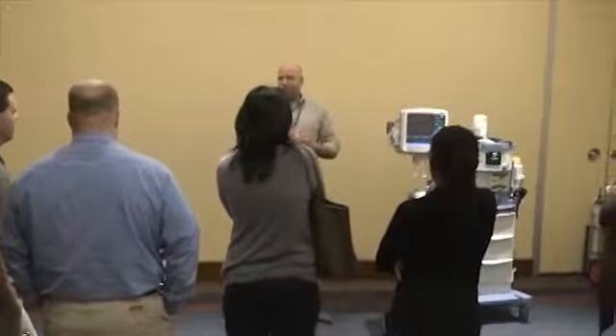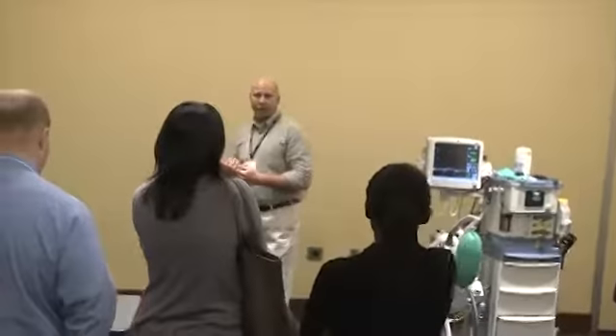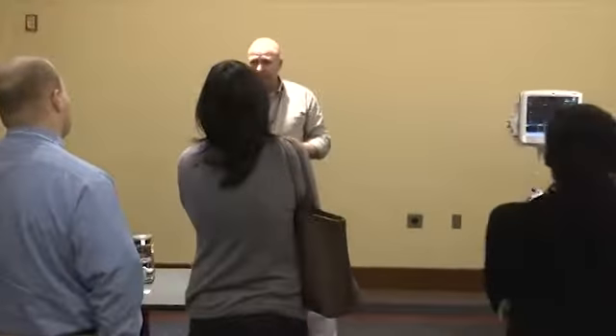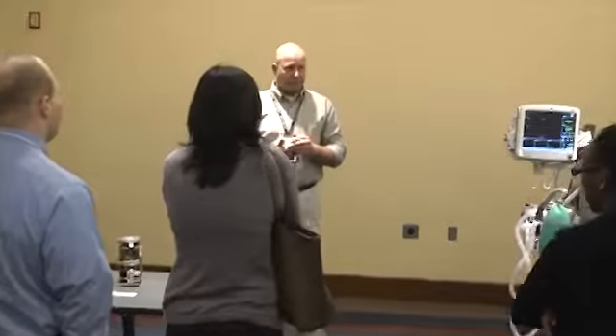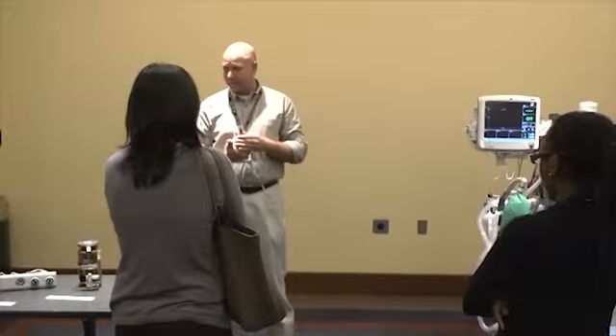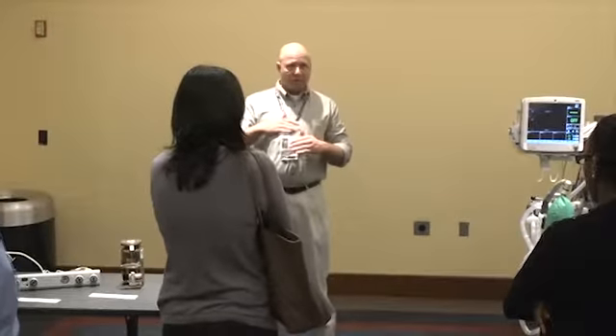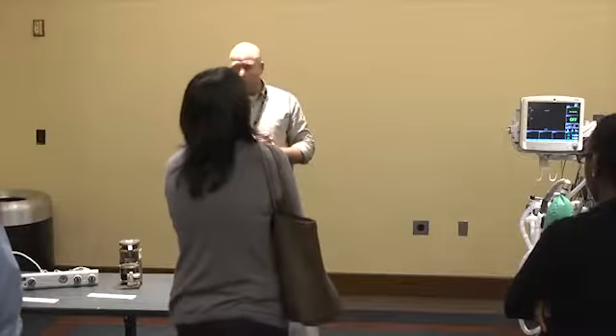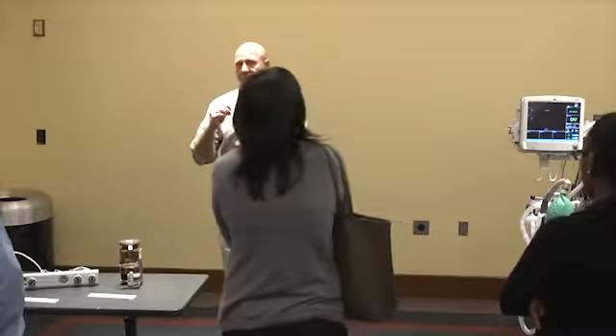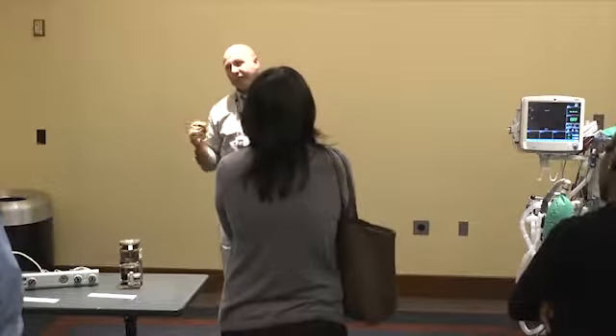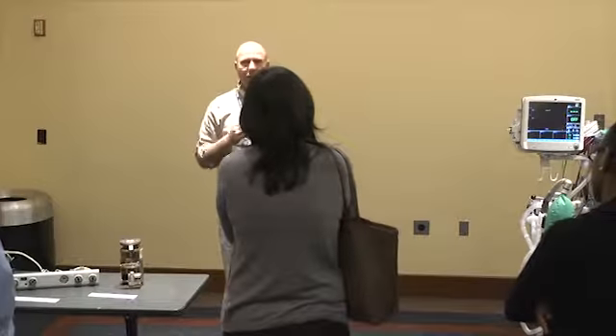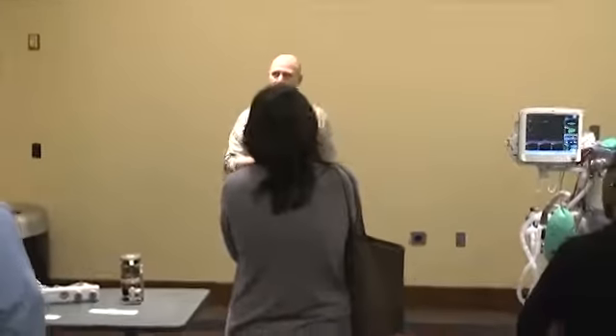You have O2, N2O, and medical air coming out of your wall or your E-cylinders. They go into your anesthesia machine at approximately 50 PSI. You try to run a range of 45 to 53. When it comes into your machine, the very first device, and you're going to want to remember this one, this will be on your quiz, you'll run into an oxygen failure protection device.